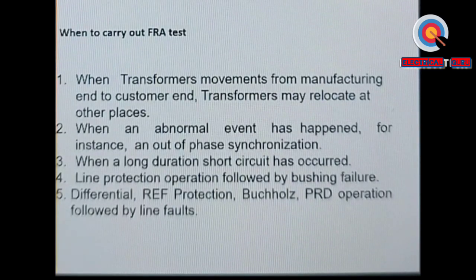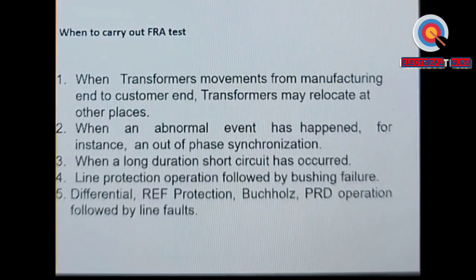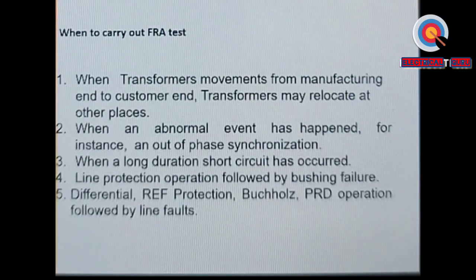So now, when do you carry out the SFRA test? When transformers are moved from the manufacturing end to the customer end, they may be relocated to other places. When we are shipping large transformers, as I told you in the beginning, on the road the transformer also experiences a lot of jerks, and as recorded it can be as high as 60 Gs, which is a very strong vibration or jerk. Under that movement, the transformer's active part within the tank, if it is not properly anchored or fixed inside the tank, may show up when we test the transformer on arrival.